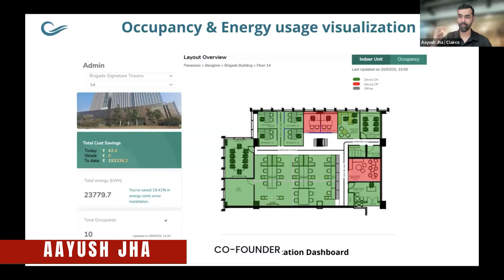While marrying your air quality data, which continues to be the base of this and is extremely important, you also have to look at thermal comfort. It's common sense: if it's a 10-pax meeting room with 10 people, the odds are the carbon dioxide level will increase and the room will become warmer. At that time, based on occupancy, we can keep the VAV open at probably 100%.